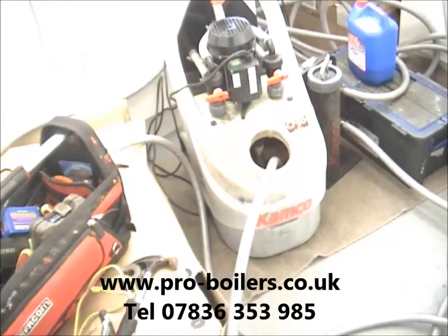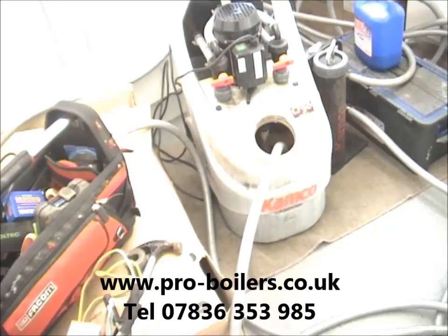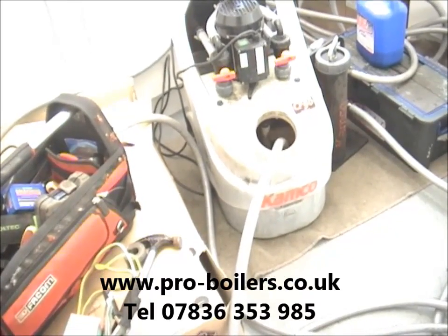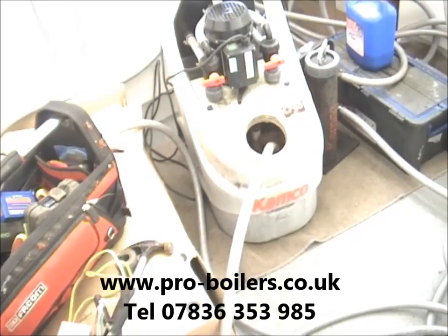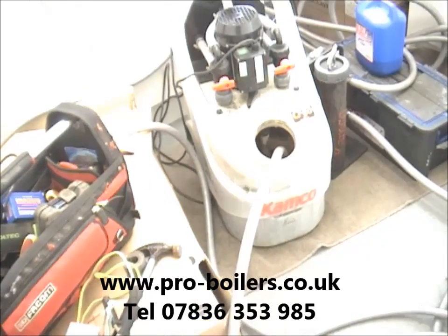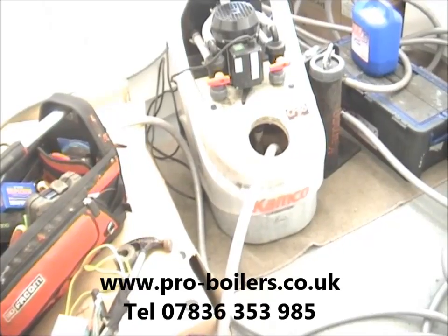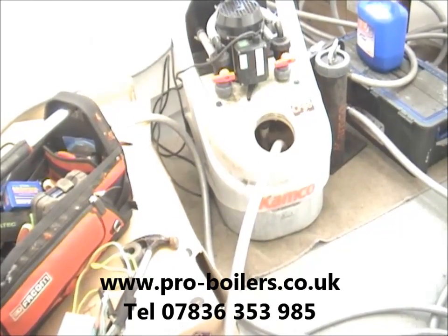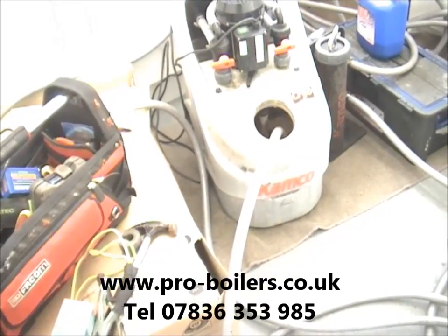If they're just running a little mains water through it with a bit of chemical, in all honesty it's just not good enough. It won't get the system clean, and you'll get all that rust and sludge running through your boiler, through your diverter valves, heat exchangers, plate heat exchangers, pump, etc., and eventually it's just going to wreck it.